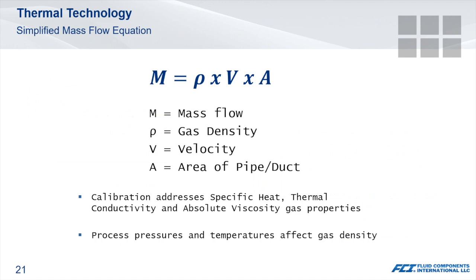As discussed earlier, mass flow is best for understanding the amount of gas being delivered or controlling stoichiometric balance of gases used in a process. An example would be the balance of air and natural gas going into an industrial burner to maximize efficiency. Looking at the simplified mass flow equation of a thermal meter, we see that the gas density is accounted for. Proper calibration of a meter will also address other gas properties that affect the cooling of the active sensor.